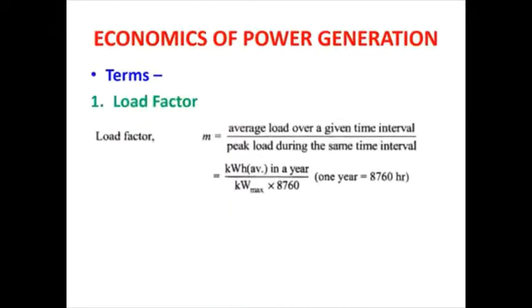So this is the formula for calculating load factor: average load over a given time interval divided by peak load during the same time interval. You can see here that it is kilowatt hours, that is average in a year, divided by kilowatt maximum into 8760. Now what is this 8760? In one day we have 24 hours, and 8760 is equal to the number of hours in one year. If you multiply 24 by 365, considering a general year, it gives us one year equal to 8760 hours.